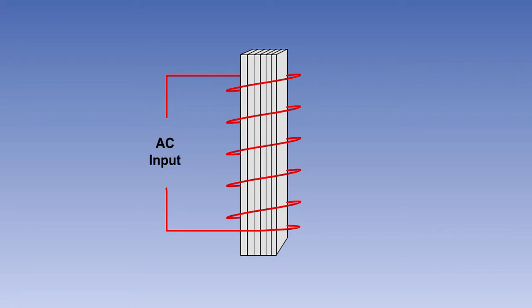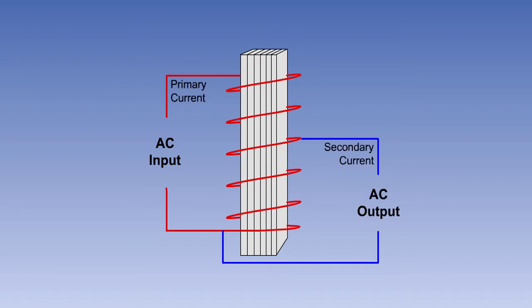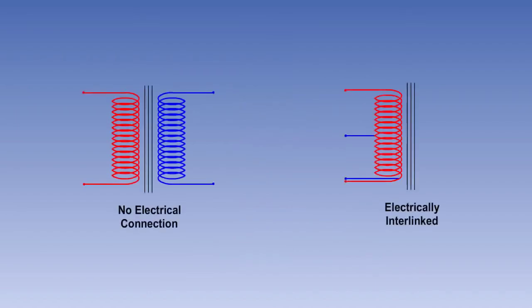An auto-transformer uses a single winding on a laminated core with a pick-off at a predetermined point along the coil. As you can see, part of the coil carries both the primary and secondary current because it is common to both windings. Auto-transformers are less expensive than two-coil transformers because they use less materials. However, one of the major advantages of two-coil transformers is that the primary and secondary circuits are electrically isolated from each other, and this is not so in auto-transformers, so their use is limited to situations where this is not important.